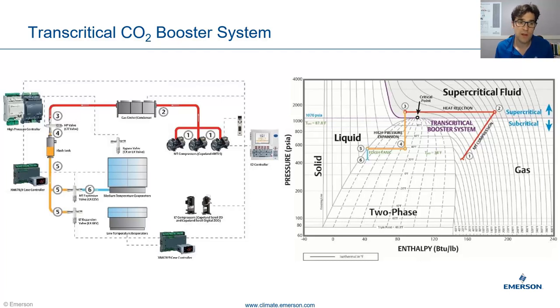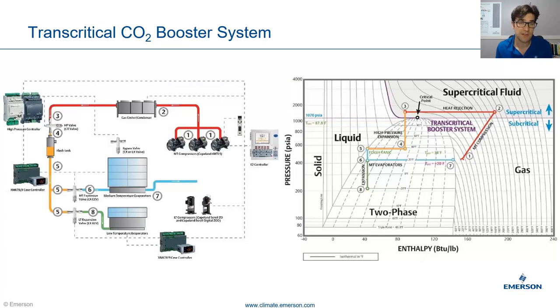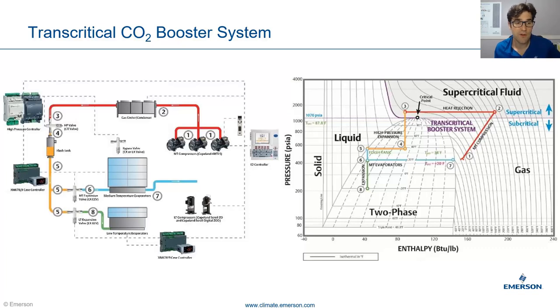That then goes back to the medium temp suction. For the low temp, you reduce the pressure even more. So that's the same liquid coming into the valve at, say, 500 PSI, but it's just dropping the pressure further — down to around 200 PSI, or around minus 20°F SST for the low temp.